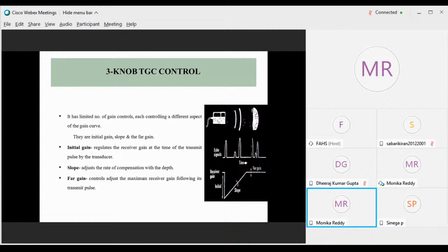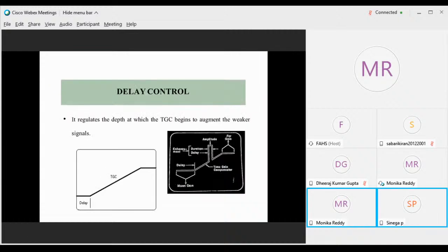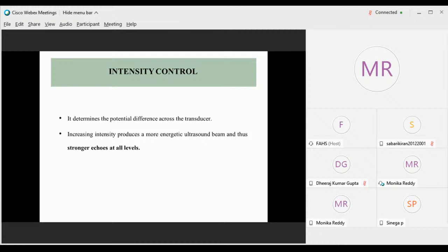Then the delay control. Delay control regulates the depth at which TGC begins to augment the weaker signals, where the signal weakening happens. From there, the delay control starts. Intensity control determines the potential difference across the transducer, and increasing intensity produces a more energetic ultrasound beam and thus stronger echo signals.